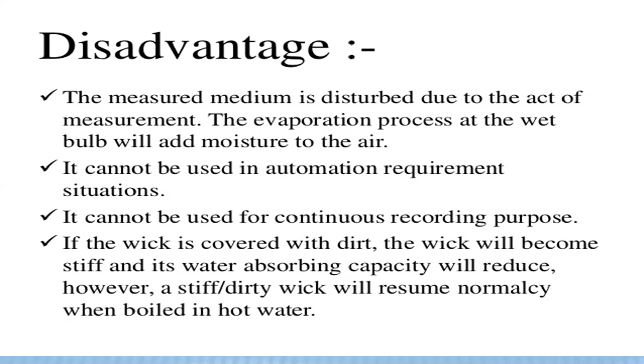It is used for checking humidity levels in air conditioned rooms and installations. It is used to check the air hygrometer. It is used in a measurement range of 0 to 100% RH, and it is used for measuring wet bulb temperature between 0 degrees centigrade and 180 degrees centigrade. So these are the applications of the sling psychrometer.